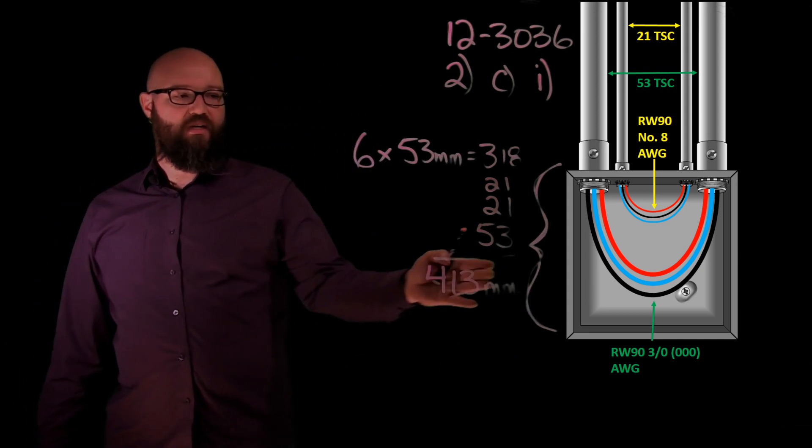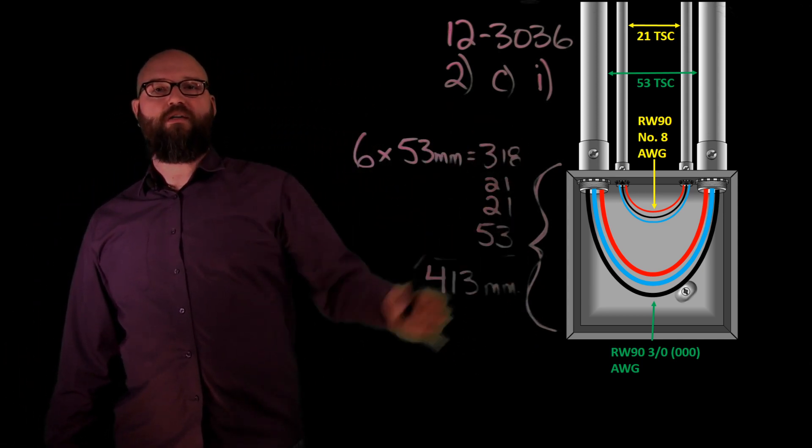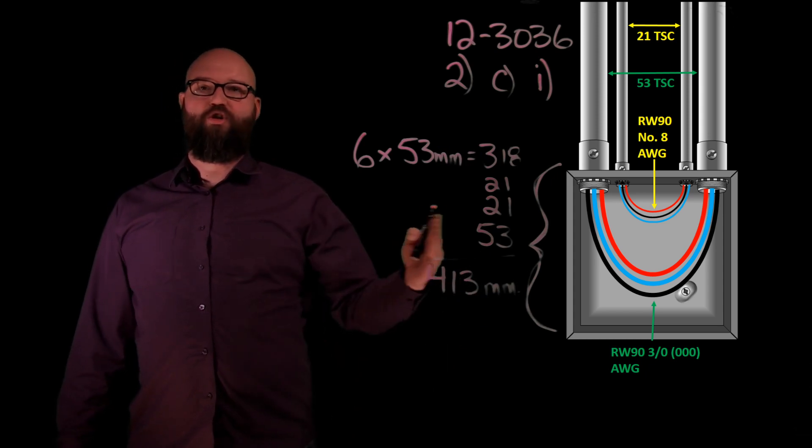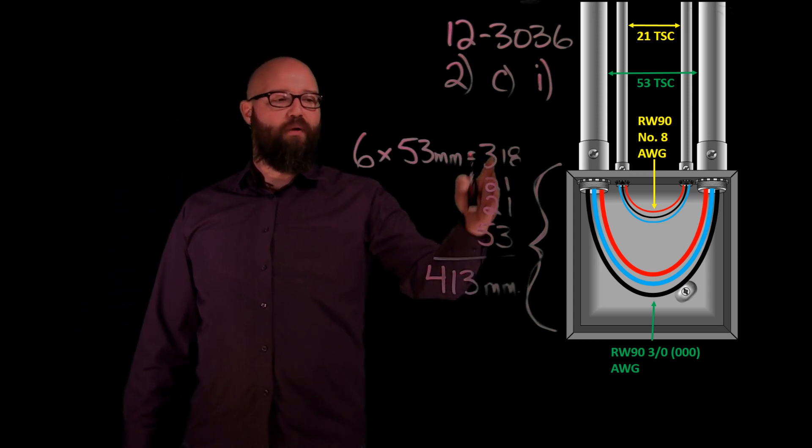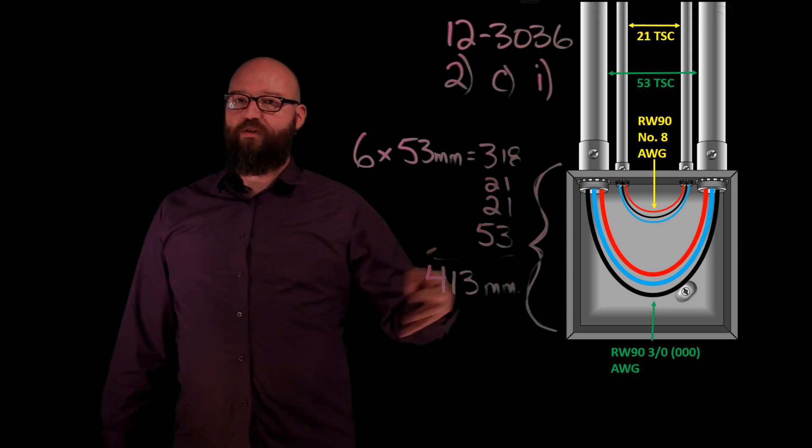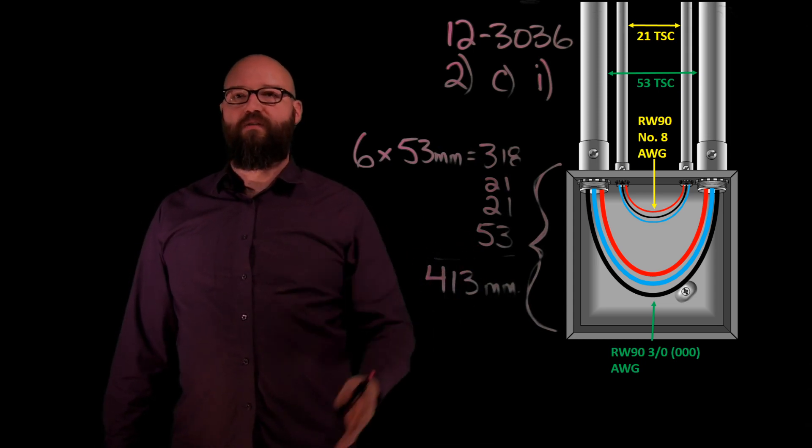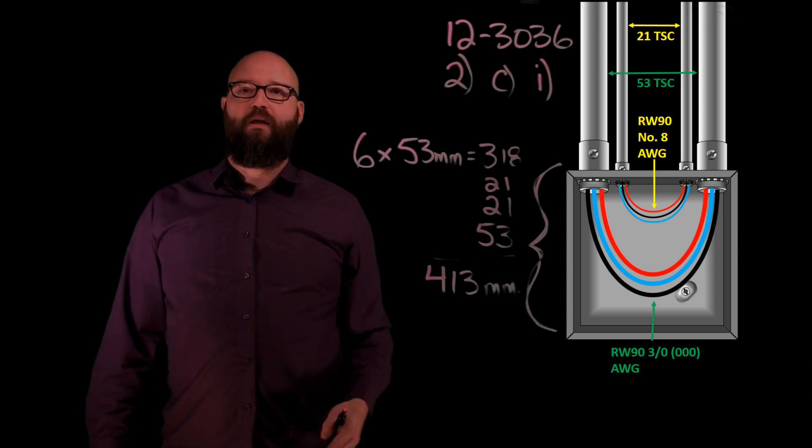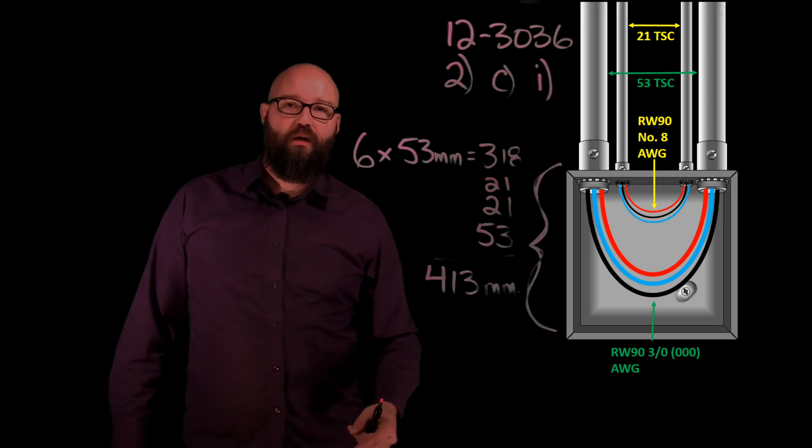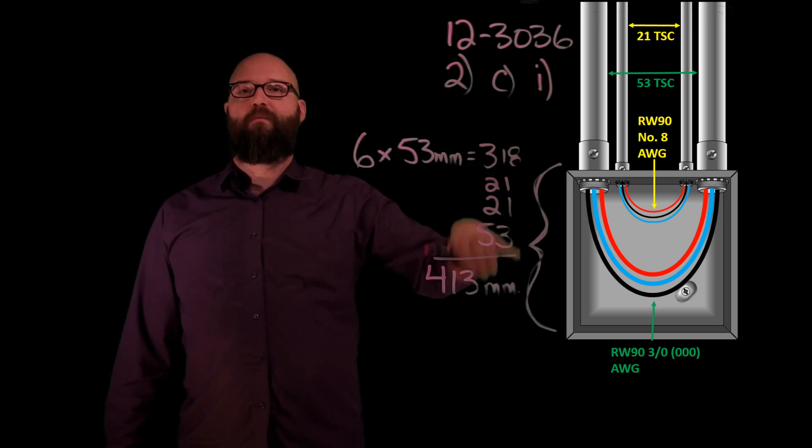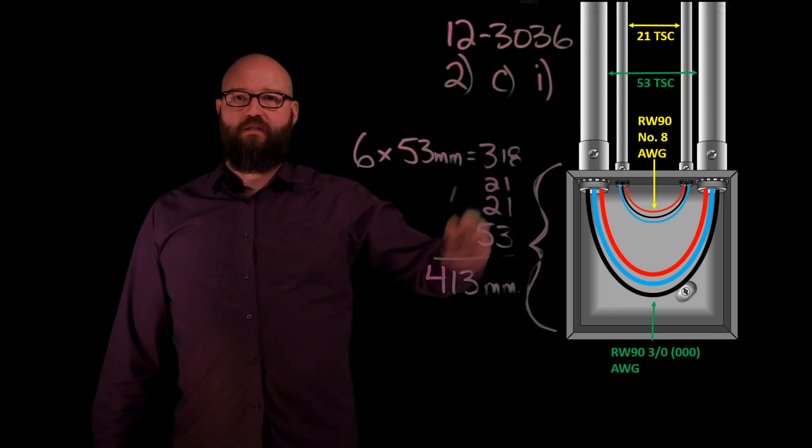That right there is the dimension of this side of the box. If I observe that, I'm ensuring that I have the proper bend radius of my conductors. If we were using a square box, the minimum dimensions of this box would be 413 millimeters by 413 millimeters. We just know that that's the minimum dimension based off of the size of these conduits.